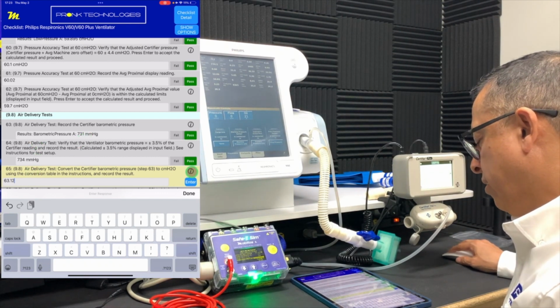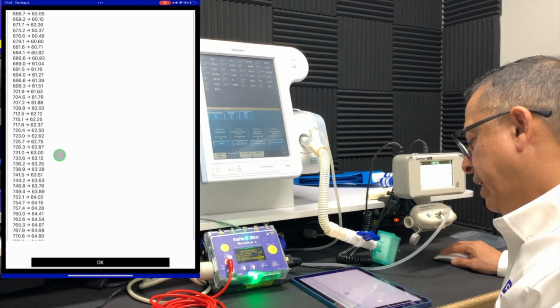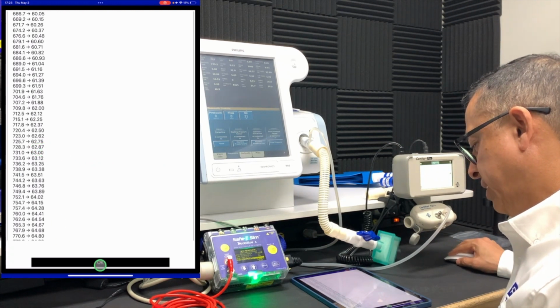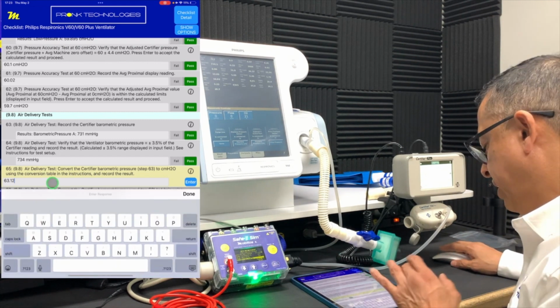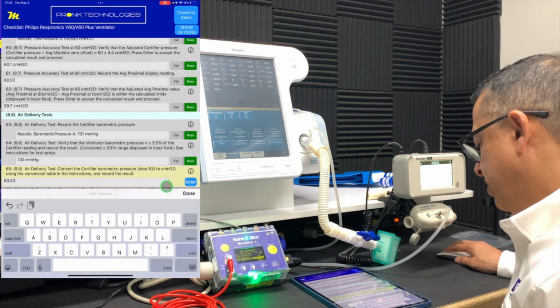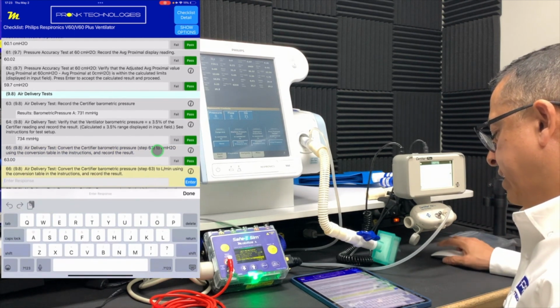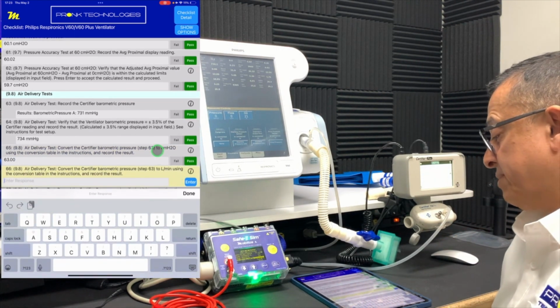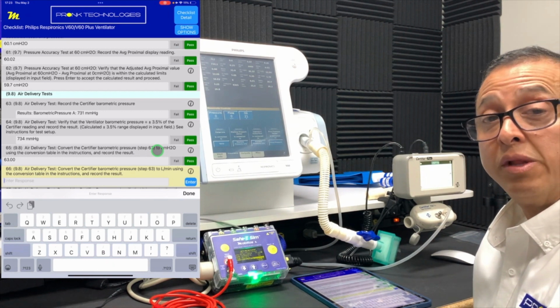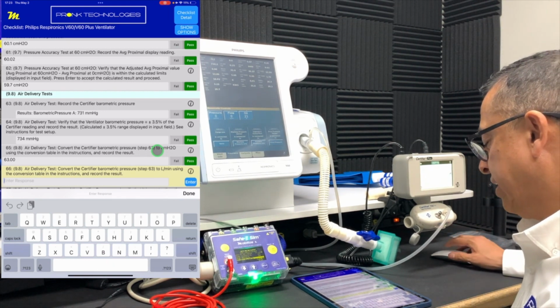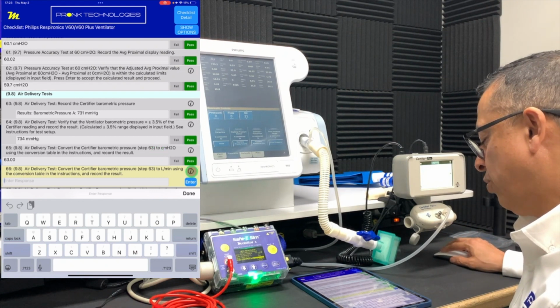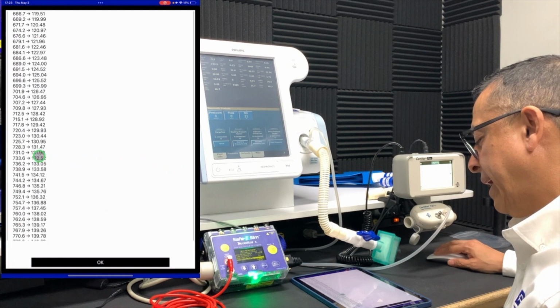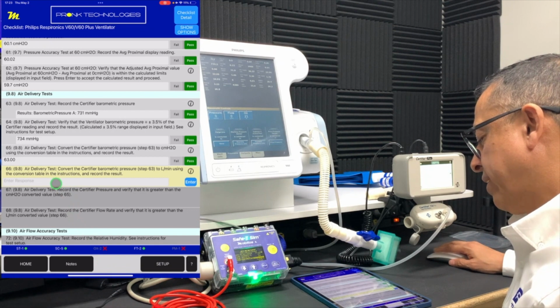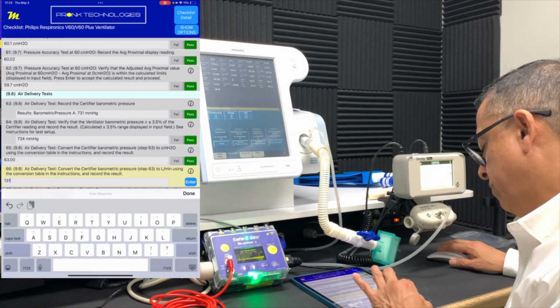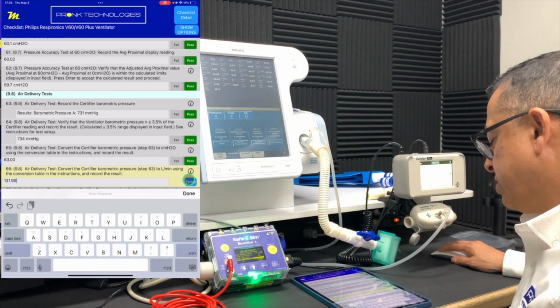So I've done that, value of 731. Double check our work here. Go back to the table, 731. It is at 63 even actually, see? Good thing to double check. So we'll make it 63 even and get that into our report. Now we're going to go on to the next step, which is we also need to convert that same step that's in millimeters of mercury, 731 millimeters of mercury. We need to also convert it into liters per minute using that same information table. I want to look up 731 and it converts over to 131.99. So I'll enter that in here, 131.99. So we've captured those conversions.